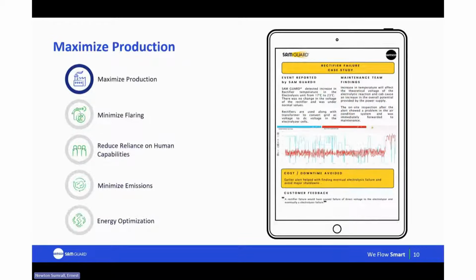So here's what happened. SAM GUARD detected a temperature increase in a rectifier for an electrolysis unit. It went from 17 degrees C to 23 degrees C. And while that's not a massive jump, it's worth noting that because the rectifier's voltage stayed steady and within normal operating limits, that's why the alert was sent. So just as a refresher, the rectifier works alongside a transformer to convert AC voltage from the grid into DC voltage for the electrolyzer cells. Catching small changes like this can help us avoid a bigger problem down the line.